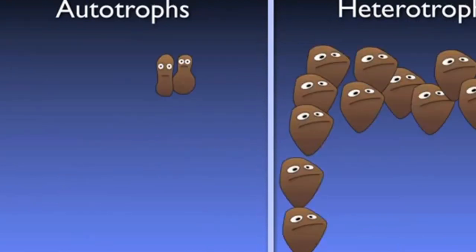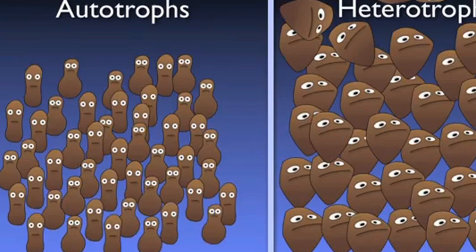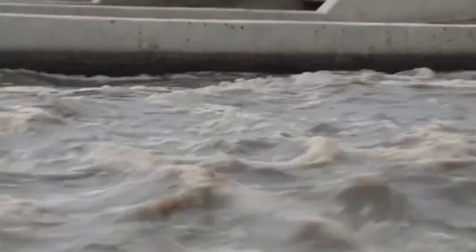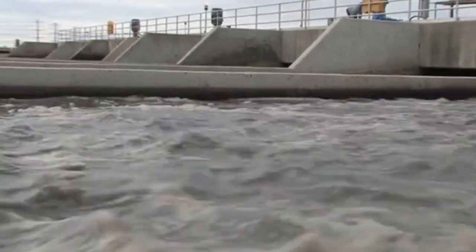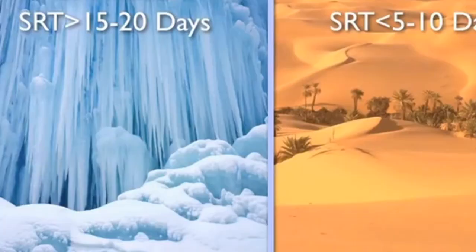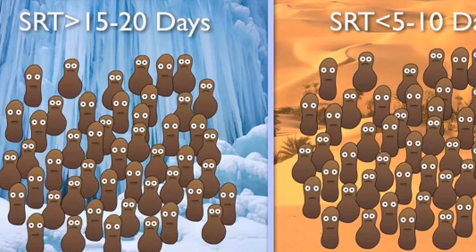In contrast to heterotrophic BOD-consuming bacteria, autotrophic nitrifiers require more time to mature and maintain their population in a biological wastewater treatment system. The nitrifiers dictate the SRT in nitrogen-reducing plants. How fast nitrifiers grow depends on the temperature of the wastewater and the amount of dissolved oxygen present. Higher temperatures and DO concentrations mean faster growth; colder temperatures and lower DO concentrations mean slower growth.